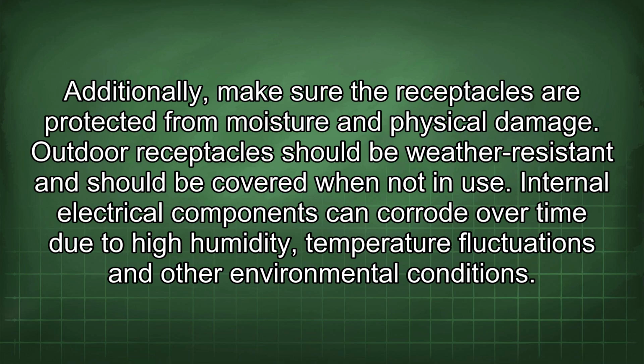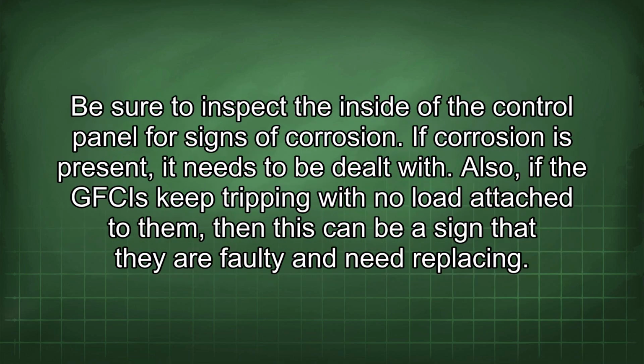Internal electrical components can corrode over time due to high humidity, temperature fluctuations, and other environmental conditions. Be sure to inspect the inside of the control panel for signs of corrosion. If corrosion is present, it needs to be dealt with. Also, if the GFCIs keep tripping with no load attached to them, then this can be a sign that they are faulty and need replacing.